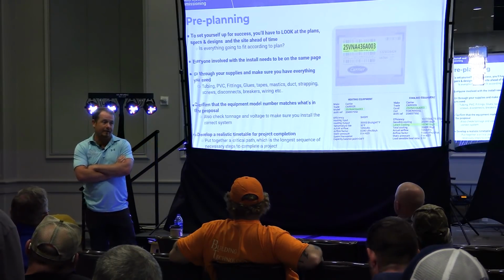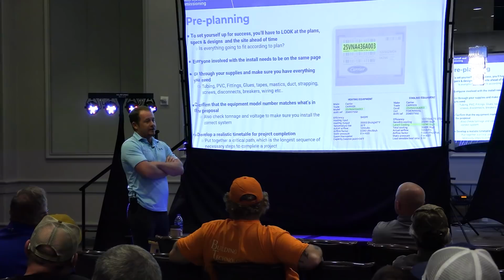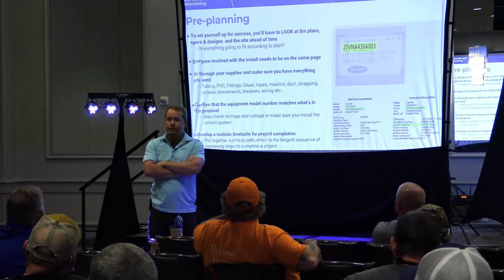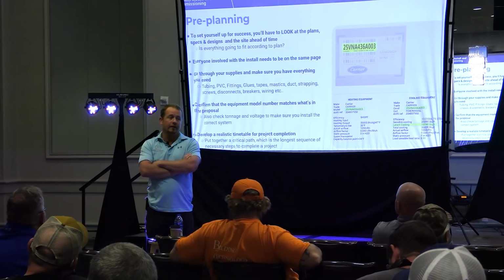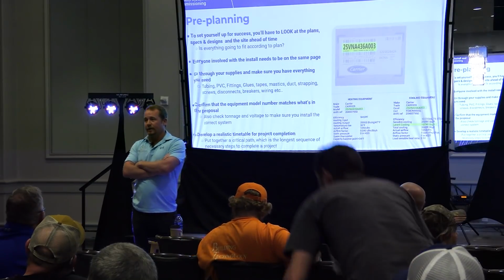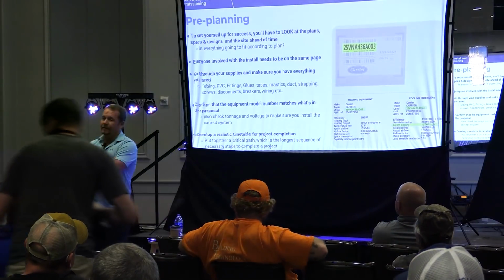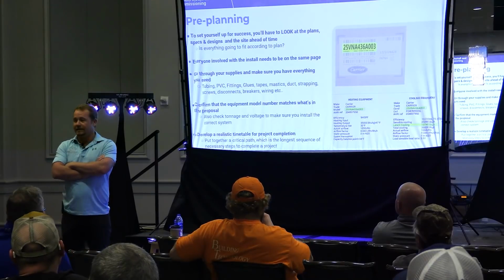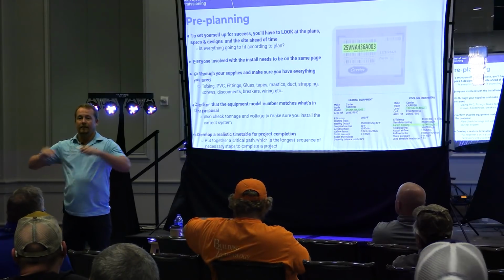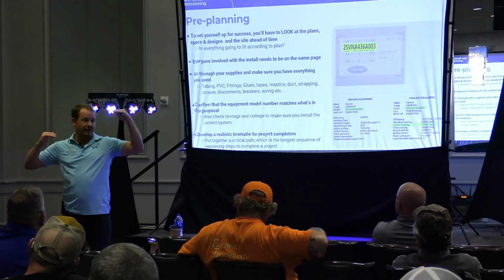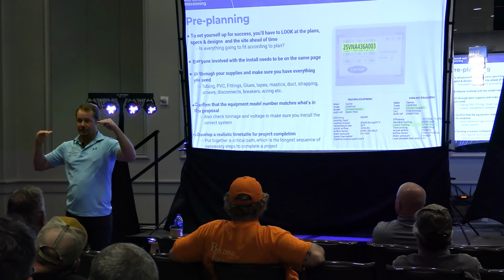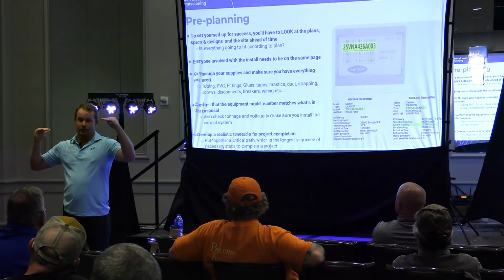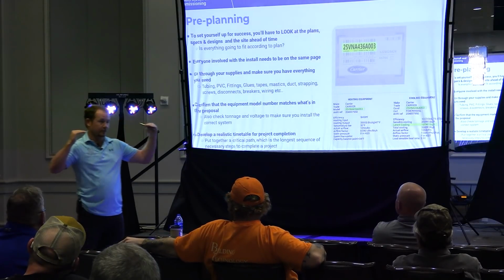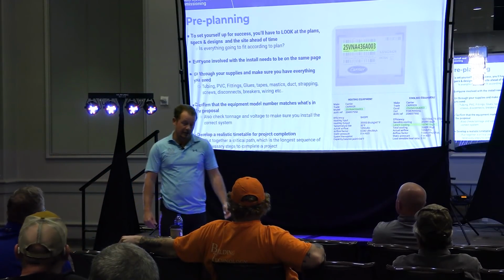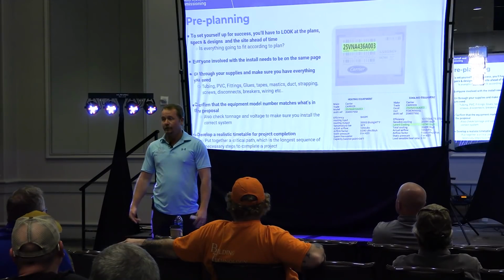You probably won't anyway, but in our market that's a major problem. So here's what you do: choose ductless systems based on a tested sensible heat ratio value at an unloaded condition. In plain words, when the set point temperature and room temperature get close together and it's still running, make sure it's still got a good sensible heat ratio. Using something like MeasureQuick, that's actually very easy to check. If you can find one, use that.